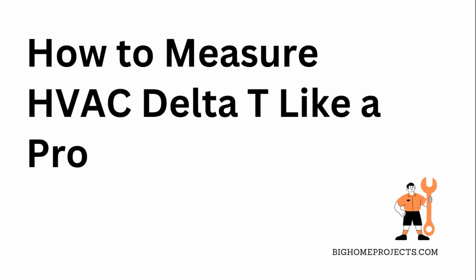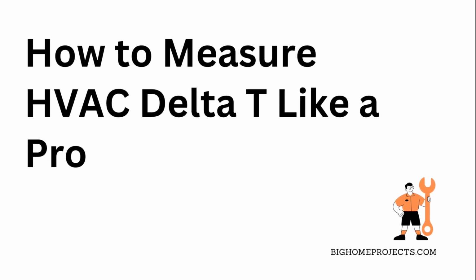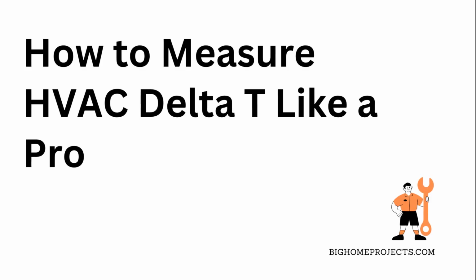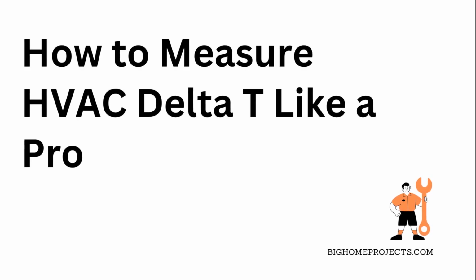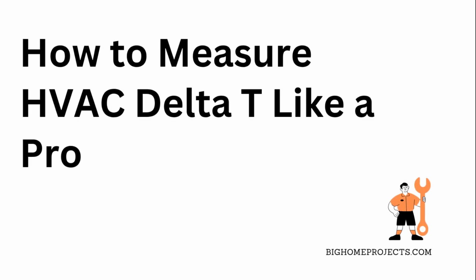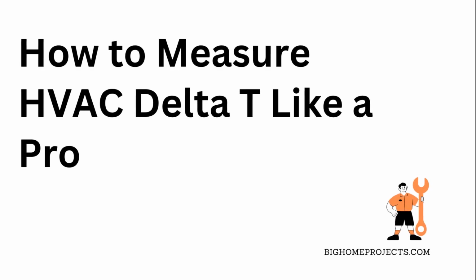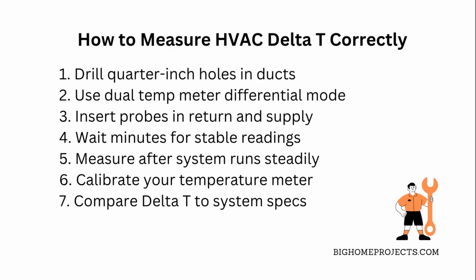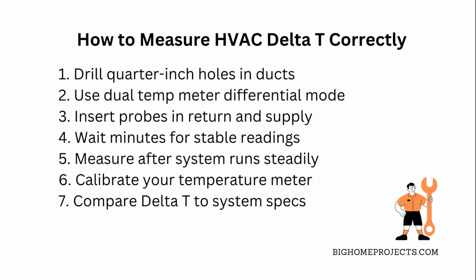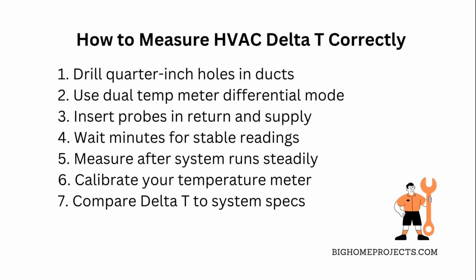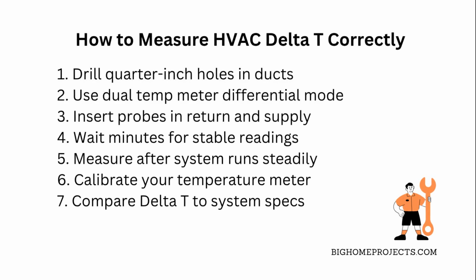Understanding HVAC Delta T is key to checking if your heating or cooling system is actually working right, and knowing how to physically measure return and supply duct temperatures makes it way easier to figure it out. So, first off, you want to find the right spots on your ducts to measure. Usually, this means drilling quarter-inch holes in both the return and supply air ducts. Just enough to fit your temperature probes in without messing up airflow.